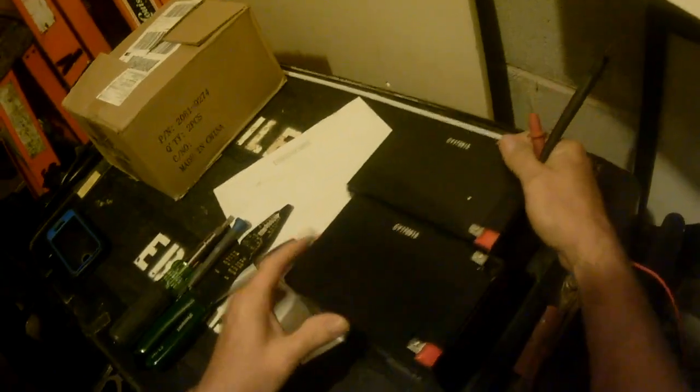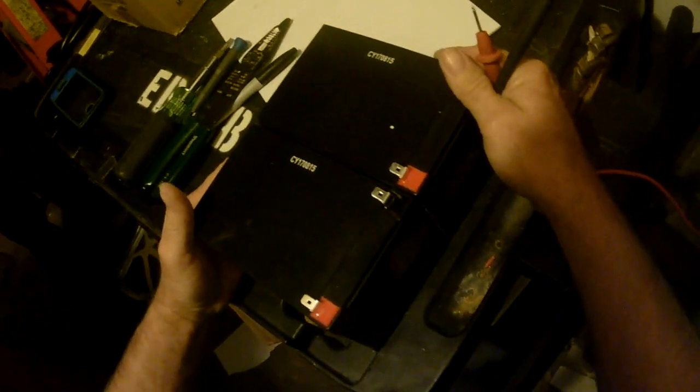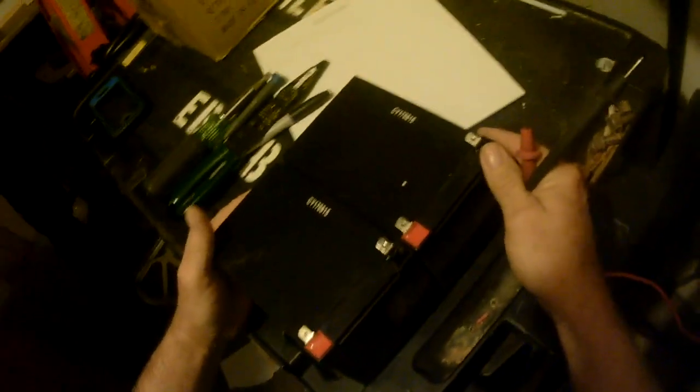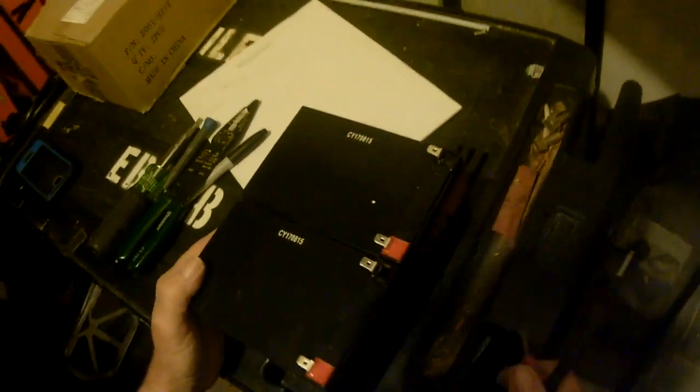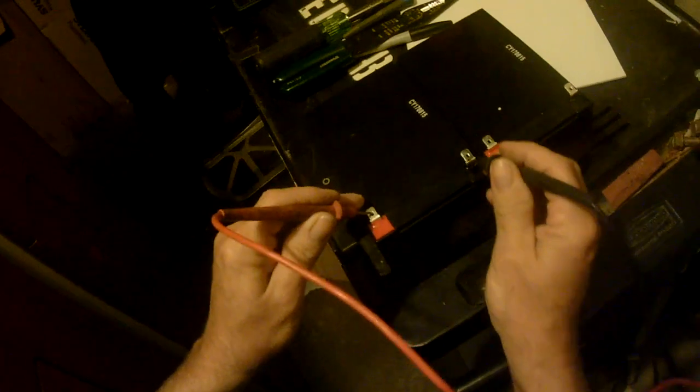I like to put them back in the original box and now we can take these old batteries and turn them back in. All right, now first of all, let's check the new batteries. You always want to replace these as a pair. You don't want to get two odd batteries or batteries of different years because the weaker of the two batteries will always call for a charge and never charge the better battery.